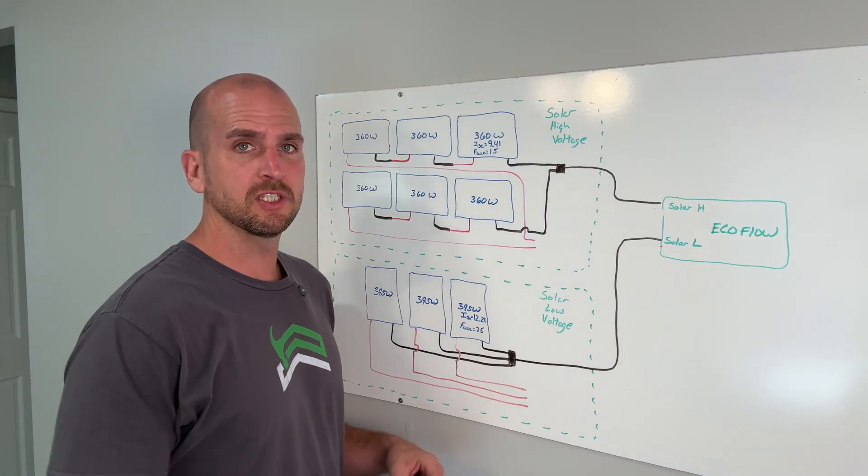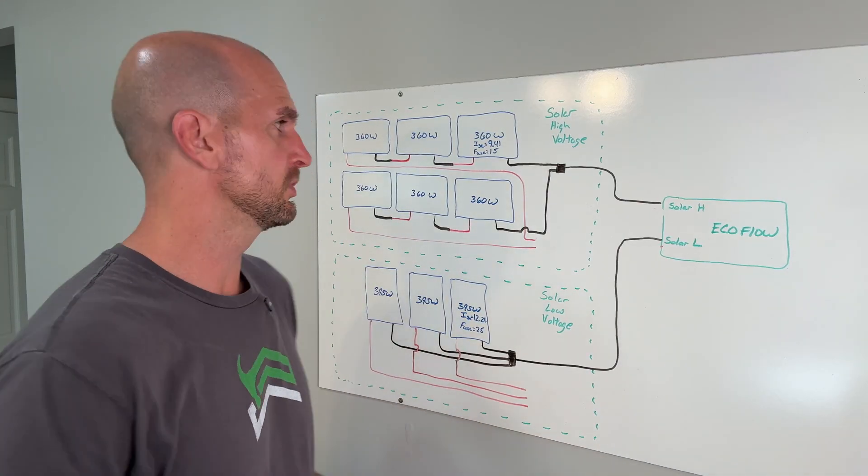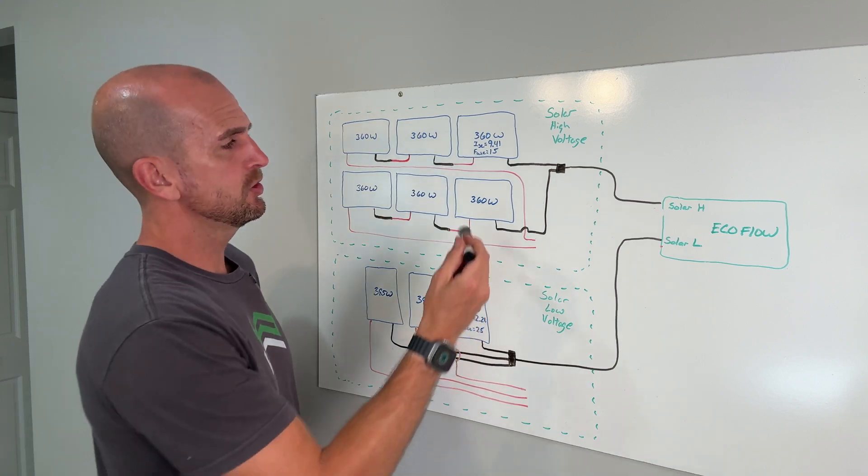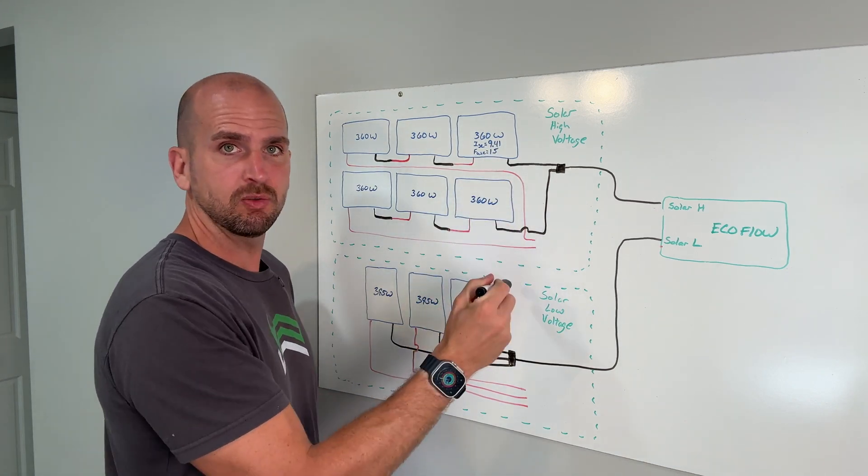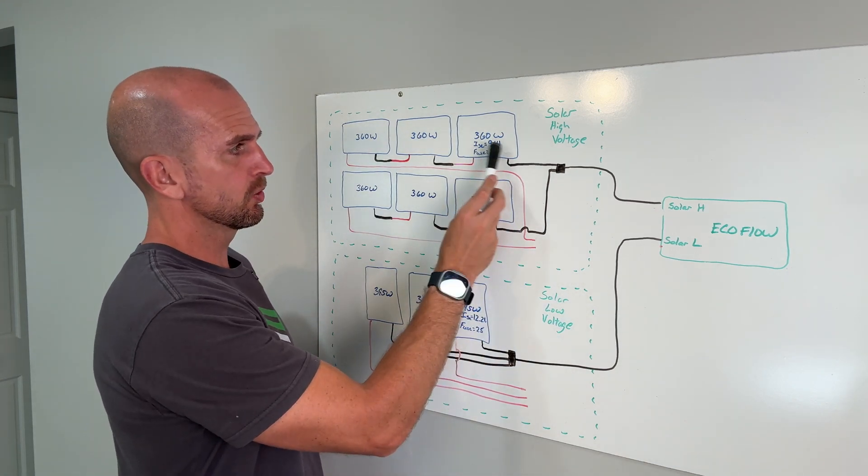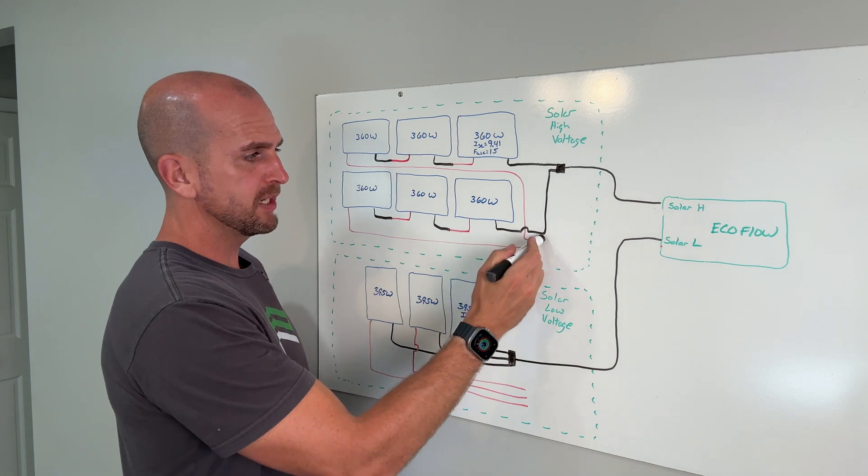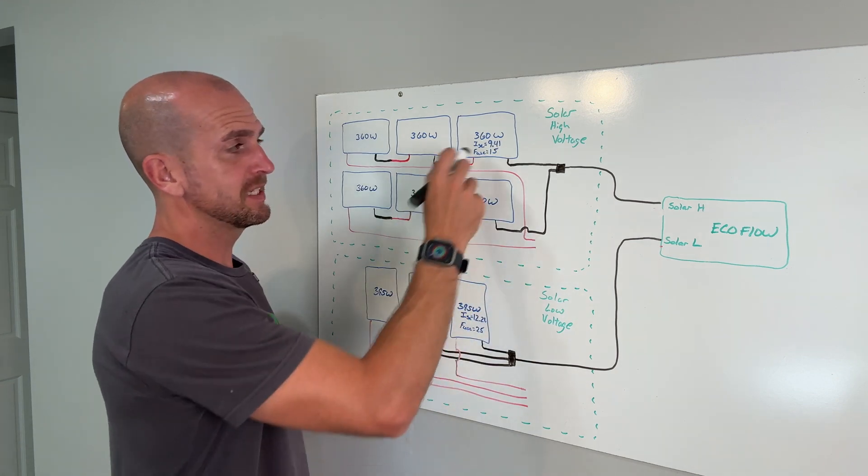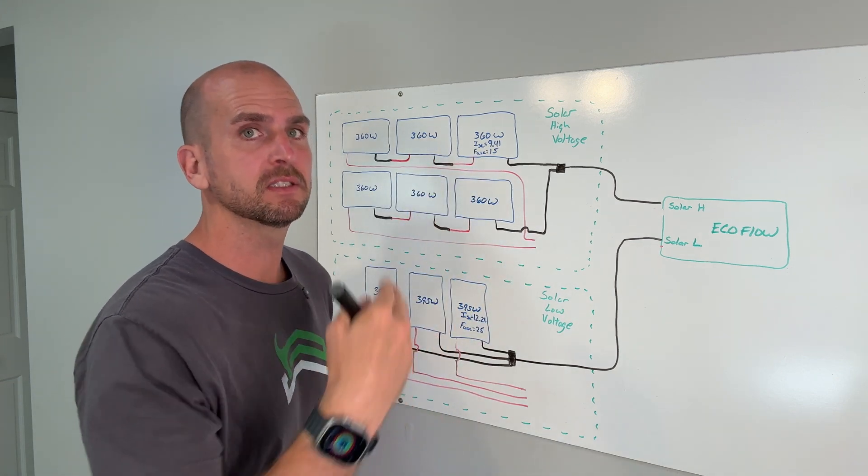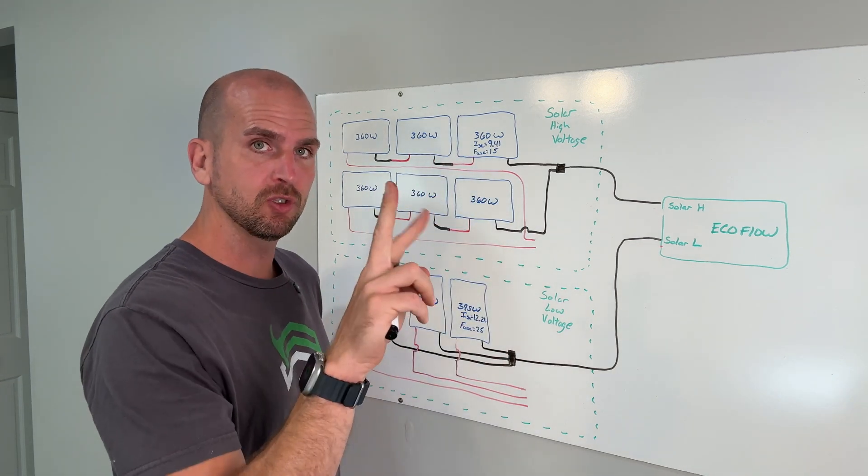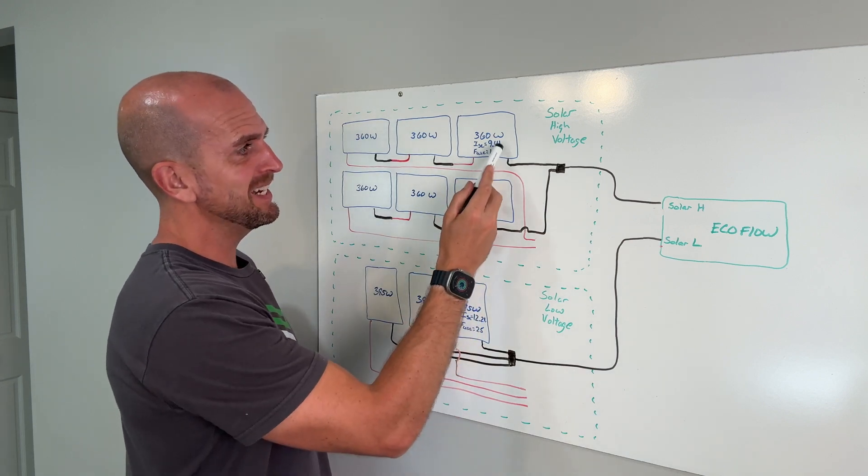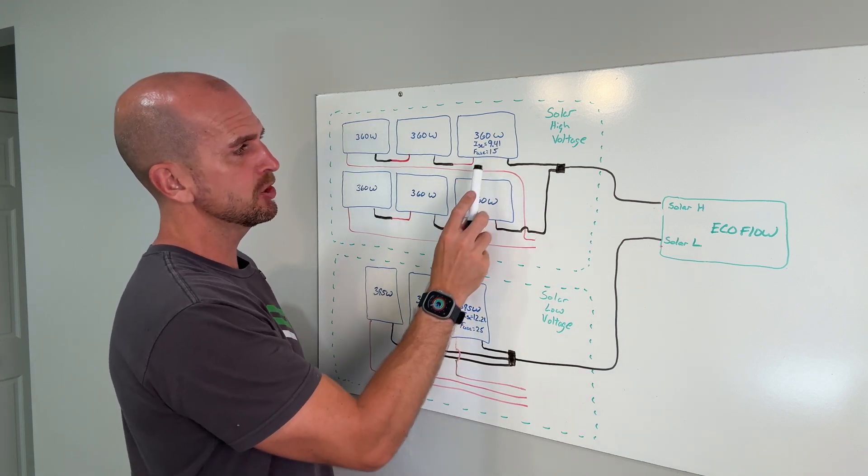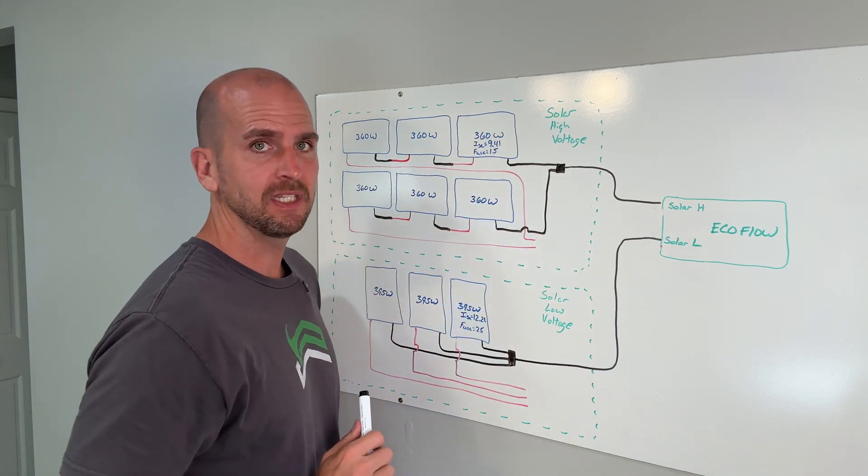With those specifications now we'll determine do we need fuses. What you do is just look at how many branches do I have and then look at your short circuit current. Two branches here so I take 9.41 plus 9.41 across those two different branches. That's going to give me 18.82 which is more than my 15.